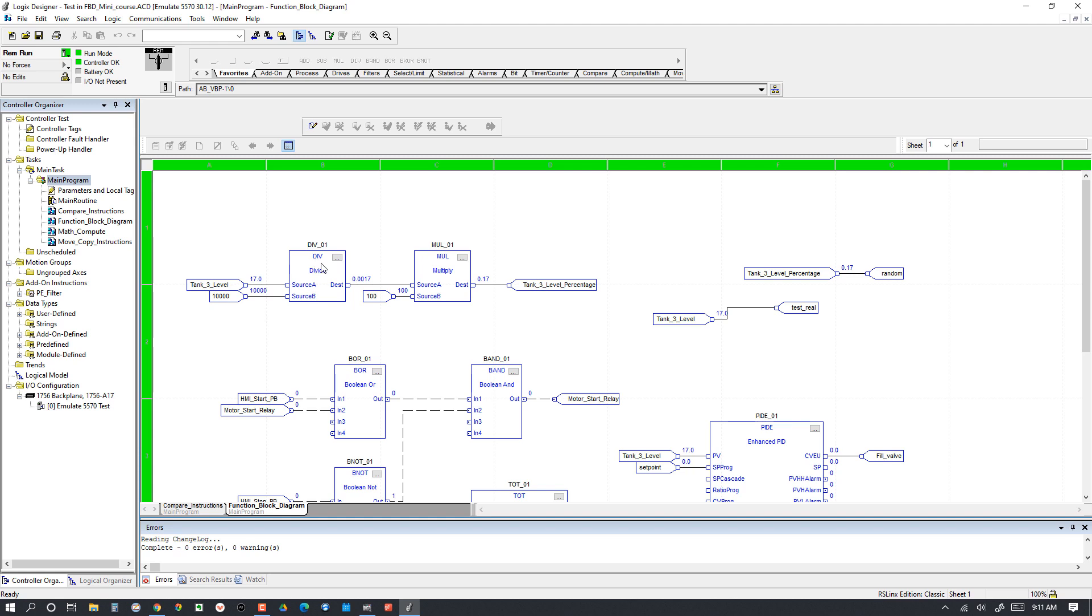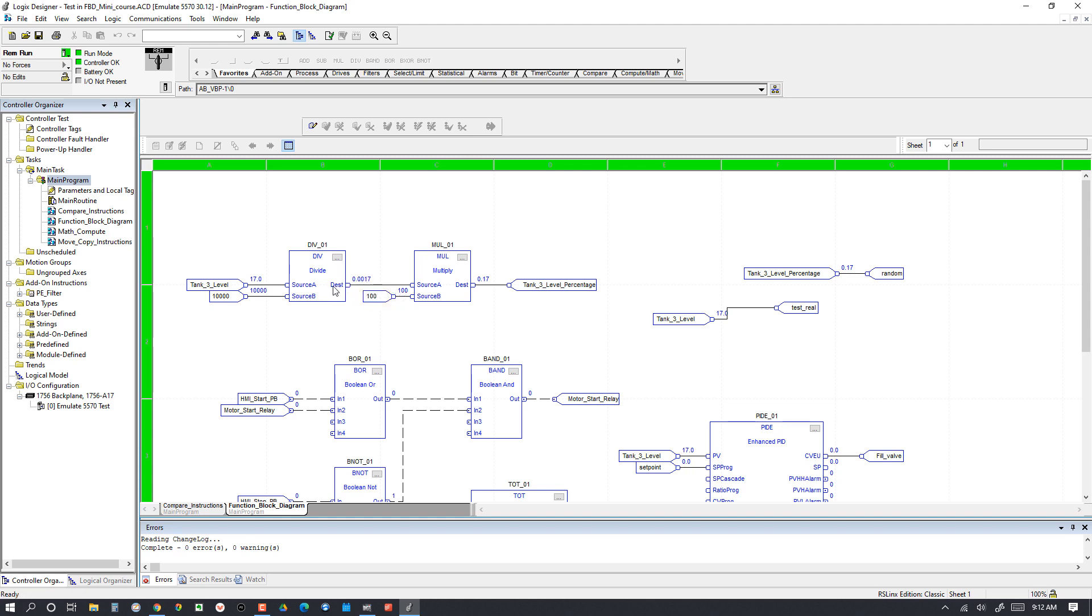What we've got is Tank 3 Level going into Source A of this Divide instruction, and the number 10,000 is going into Source B. The Divide instruction just takes Source A, divides it by whatever is in Source B. In this case, it looks like Tank 3 Level is 17. So 17 divided by 10,000 is going to be put into the destination, which is 0.0017. We don't even have to put a tag here, which is another nice thing about Function Block Diagram. You can just connect it to another source, or you don't even have to connect it, you can just see what the output is going to be.